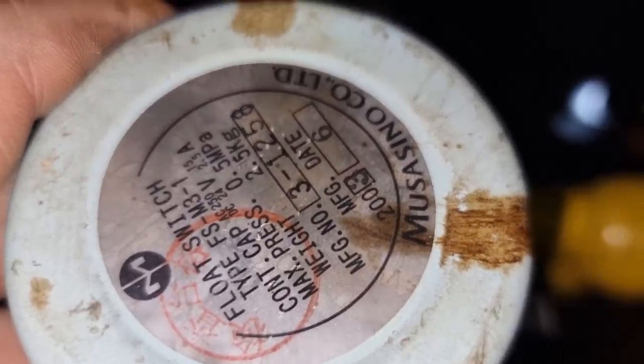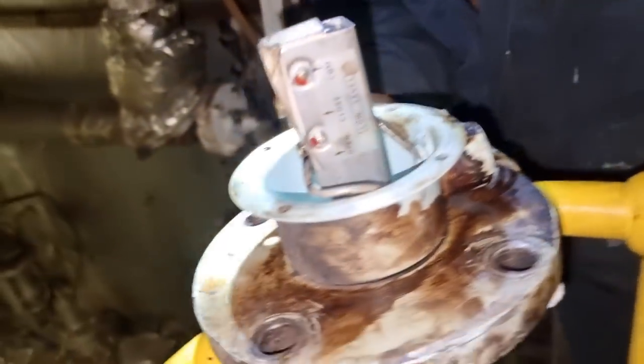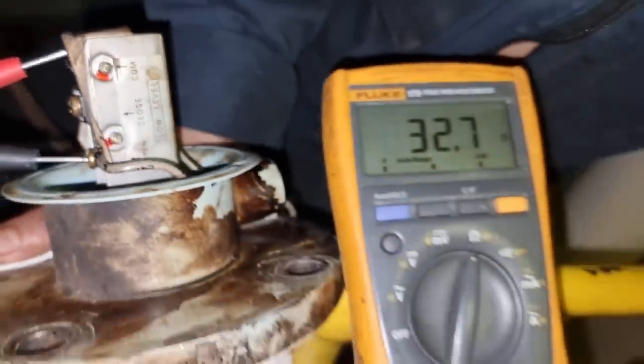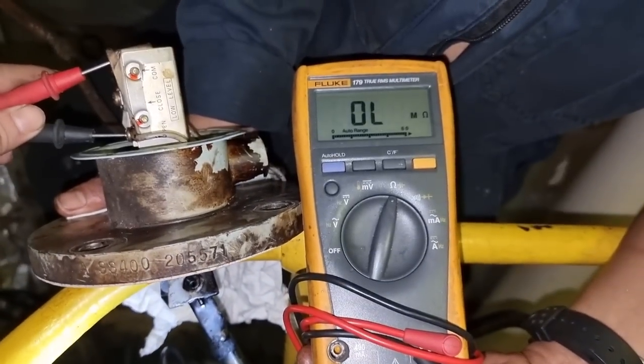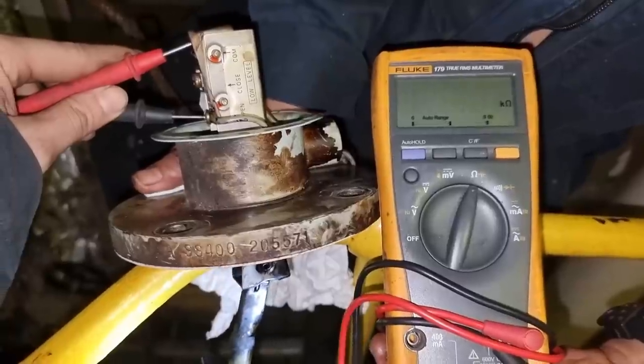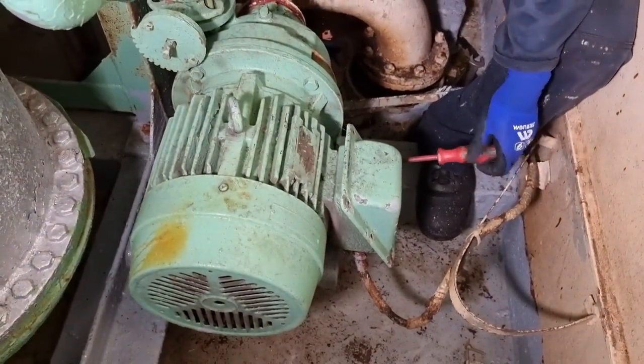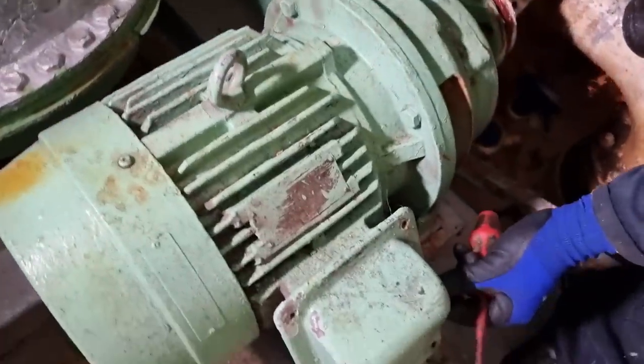I then proceeded to another troubleshooting involving our fuel oil settling tank. The alarm remained active even though we did not have a high fuel oil level. We dismantled the sensor — making sure the level was not actually in the spillage range first, since we had rolling and needed to avoid an oil spill on board. I checked the continuity of the float switch using my multimeter in resistance mode to see if it was opening and closing as I moved the float. It responded well, so the float was likely just stuck. After putting the float switch back, the alarm cleared.